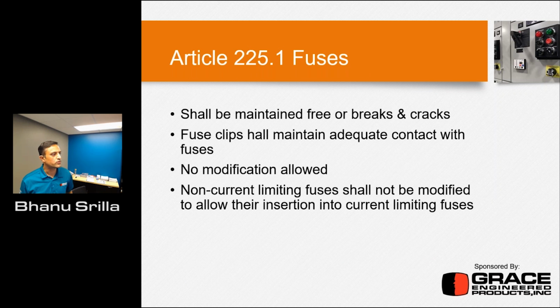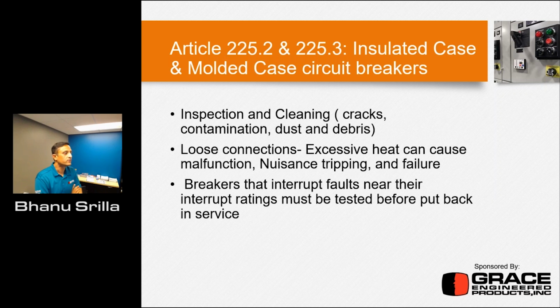And then Article 225 talks about fuses. The fuses shall be maintained and free of visible breaks and cracks. Fuse clips shall maintain adequate contact with the fuses. And last but not least, you can't make any modifications. 70E clearly states that you can't make a modification to the fuse to allow the insertion of a non-current limiting one into a current limiting one, because they serve two different purposes, period, okay? So Article 225.2 and 225.3 talk about insulated case and molded case circuit breakers.